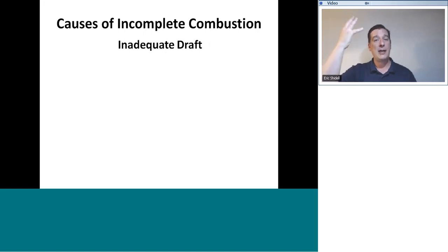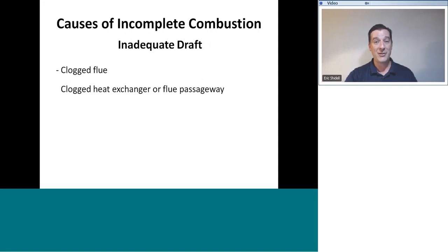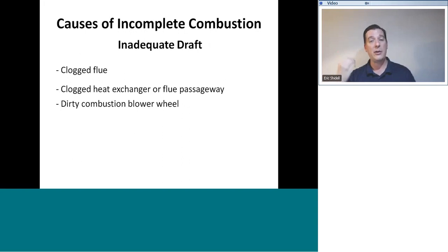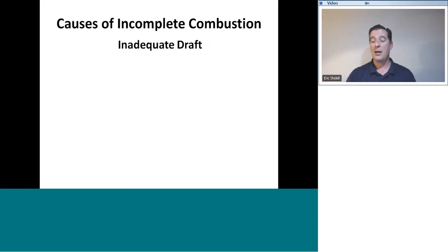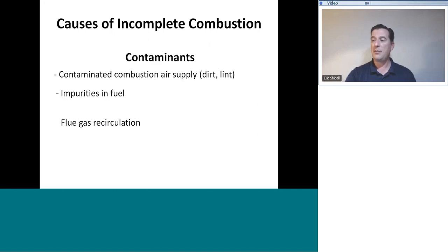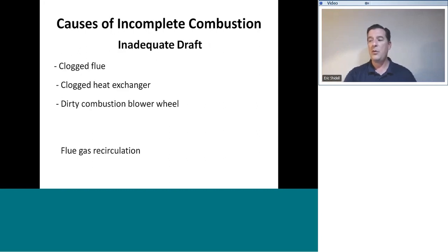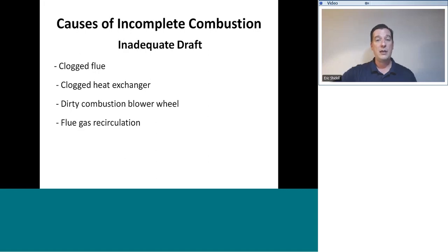Inadequate draft through the appliance. We'll talk about drafts in the second half of our program today. That can be caused by a clogged flue or a clogged heat exchanger or flue passageway inside the heat exchanger. A dirty combustion blower wheel may be spinning fast enough to make the pressure switch, but not fast enough to adequately draw the combustion products through the appliance. Inadequate draft can also be caused by flue gas recirculation. This is more common in 90% furnaces where the combustion intake and the exhaust are right next to one another. And if flue gas is allowed to be drawn into the intake, now we are going to have polluted combustion air supply.